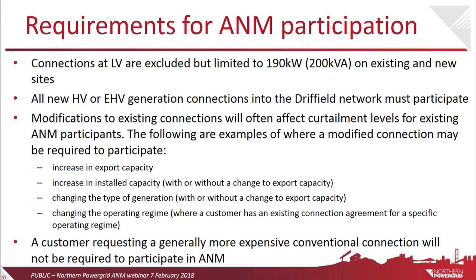So back on slide number 10, connections at LV are excluded but limited to 190 kilowatts. So if you can come in at 190 kilowatts or less, then you can get connected without joining the ANM scheme. You'll just get connected. But if you're above that limit, effectively, you've got to either join the ANM scheme or pay for reinforcement. Of course, there could be some reinforcement costs associated with connections of less than 190 kilowatts.